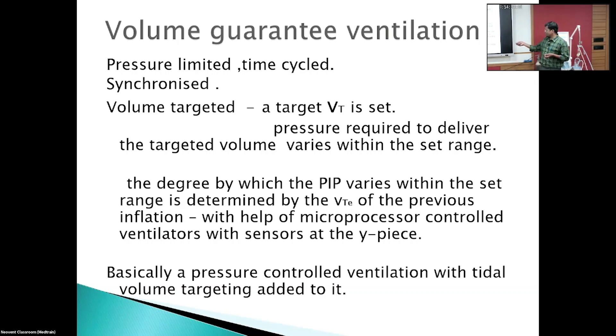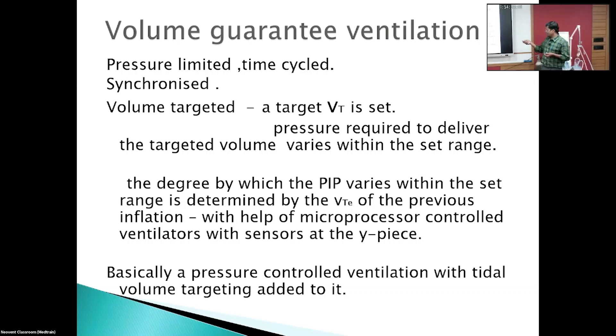The sensor present at the Y-piece of the circuit senses the exhaled tidal volume and sends it to the microprocessor of the ventilator. The PIP is then altered for the next breath according to the exhaled tidal volume sensed. It is basically pressure-controlled ventilation with tidal volume targeting added to it.